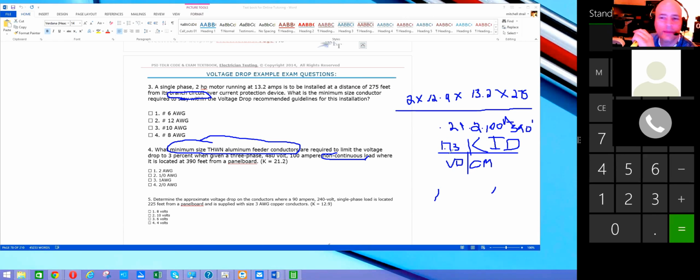You'd said something about 1.732 earlier. Again, since PSI just looks at 2 digits, we just do 1.73 instead of 1.732. It's not a significant number, but it's a difference nonetheless. So 1.73 instead of 2, because when I have 3 wires working in concert in 3-phase, my load value is going to be less than what a single phase would have. That's what this 1.732 is. It's a little smaller number than it would have been as a single phase.